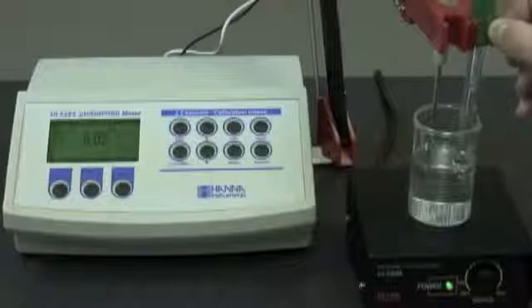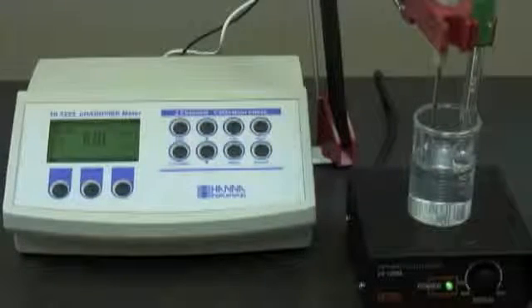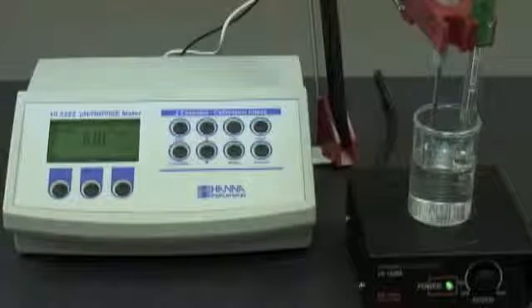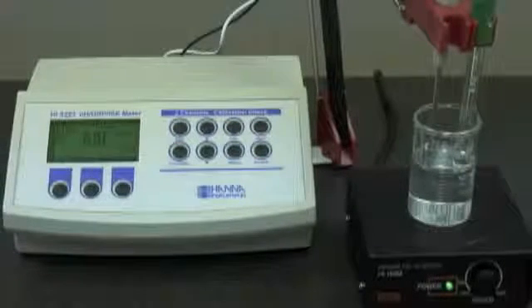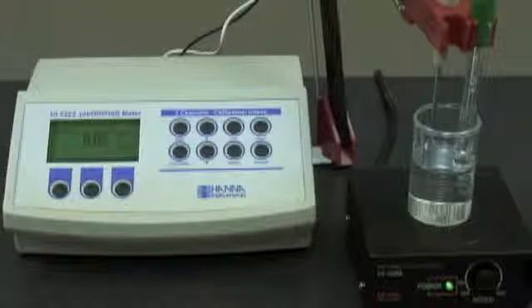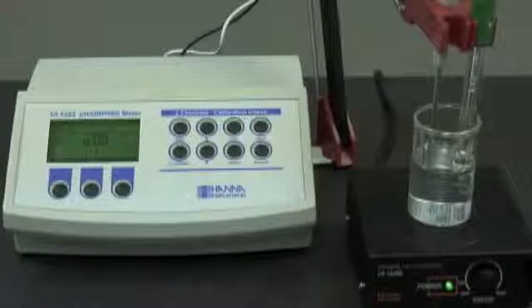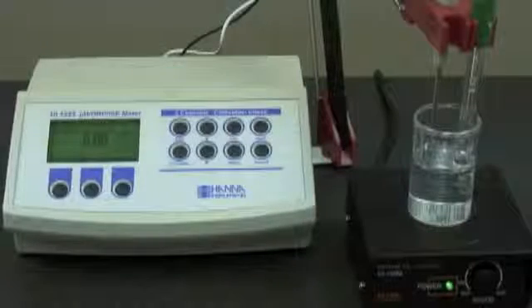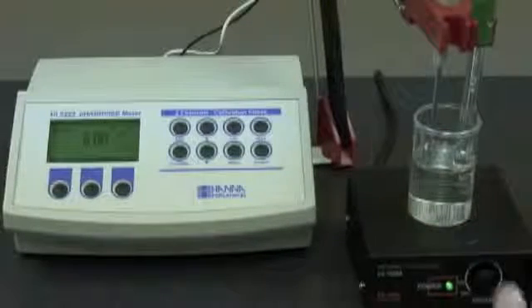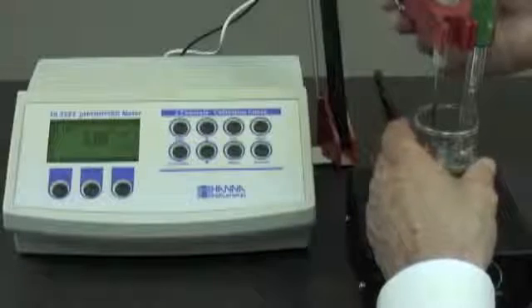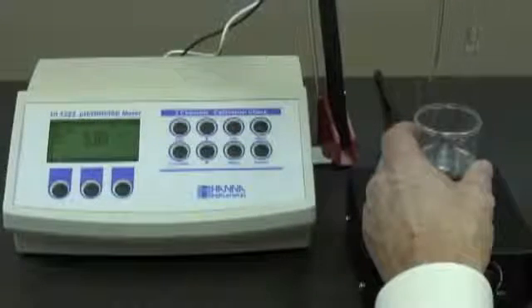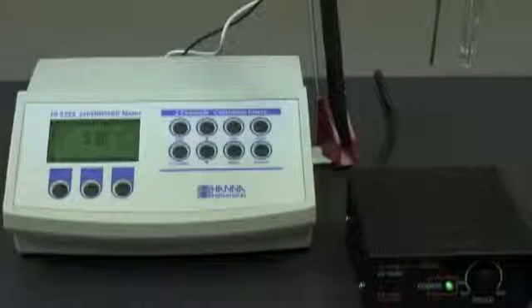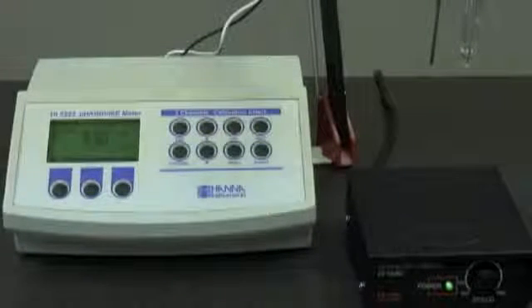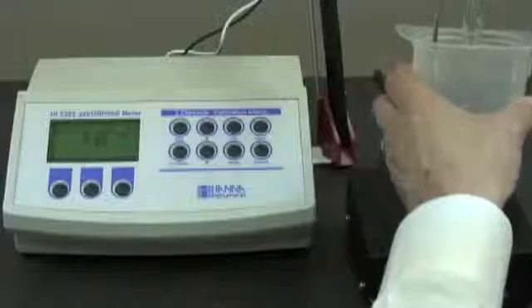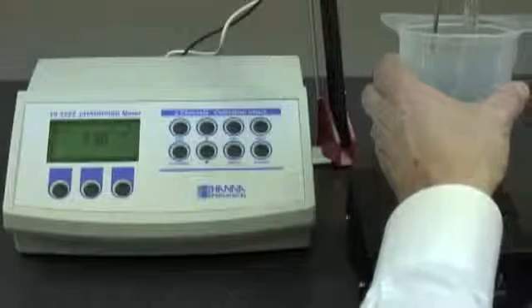So what I've done is I've unscrewed it from the probe, I've taken the cap off, and I'm going to set it aside. And the reason that I want to do that is I want to create a positive head pressure that allows for a higher flow rate through the junction, which results in a faster response time. So once I've done that and my probe is accurately conditioned, I'm going to remove the probe from the storage solution, and what I'm going to do next is rinse the probe in deionized water to get any excess storage solution off of there.